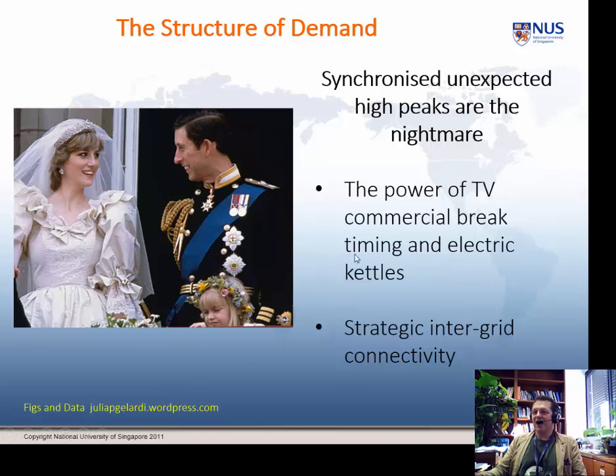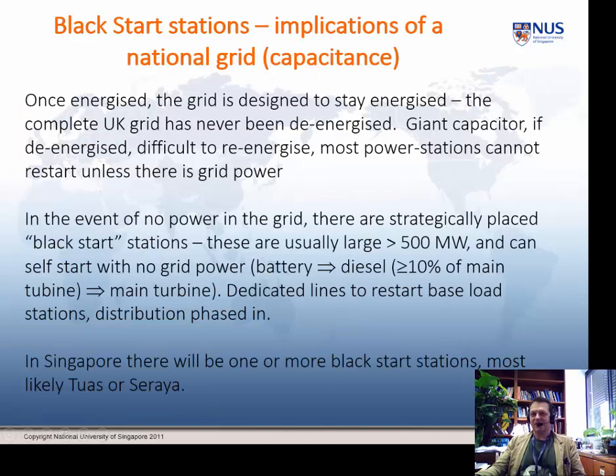I've actually got the data for what happened in that seven or eight minutes, but we came to within probably 10 seconds of a complete national power cut because the sudden unexpected demand took demand above peak. As it happened, strategically, there are these high voltage DC links, and the French would love to know this, but it was their power that kept the royal wedding on the air. How embarrassing is that? Well, embarrassing if you're English anyway.